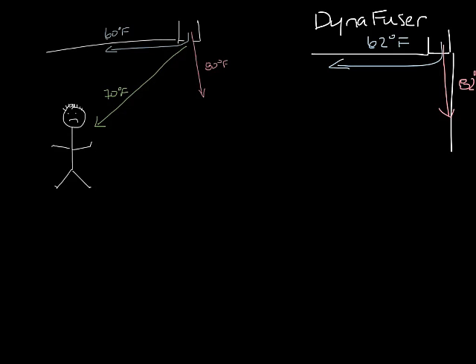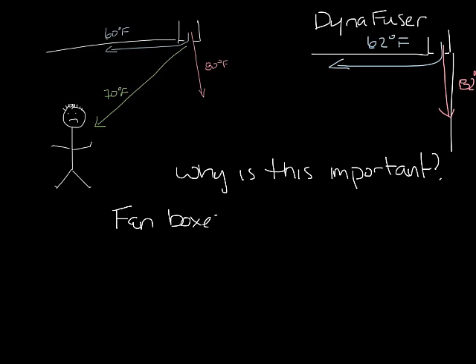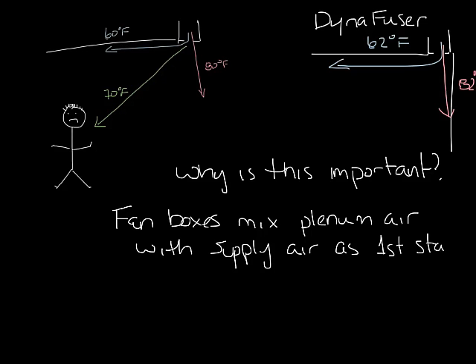So why is this two position actuation important? If you have your slot diffuser connected to a fan powered terminal unit, and if you recall from the fan box podcast the first stage of heating for a fan box is mixing plenum air with the primary air. So you could have supply air temperatures in the mid 70s quite often with a fan box. If the diffuser wasn't a two position device it could spend a lot of time in that middle range directing the air at a 45 degree angle into the space and towards the occupant.